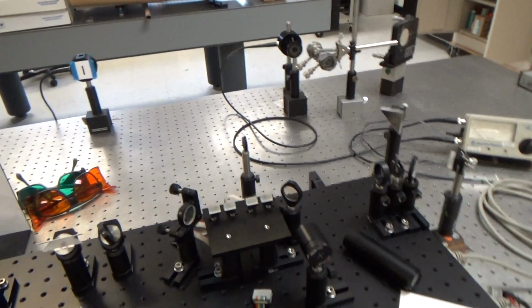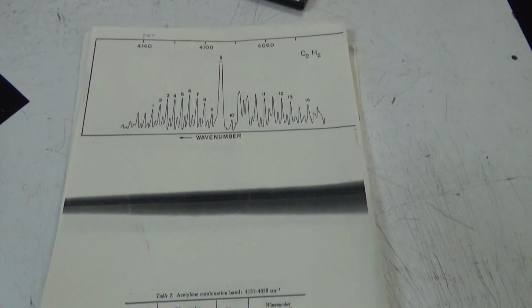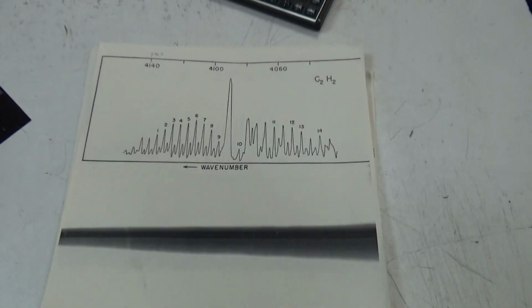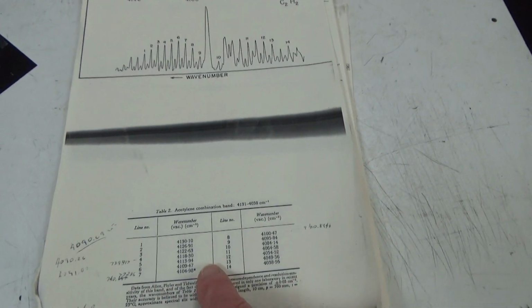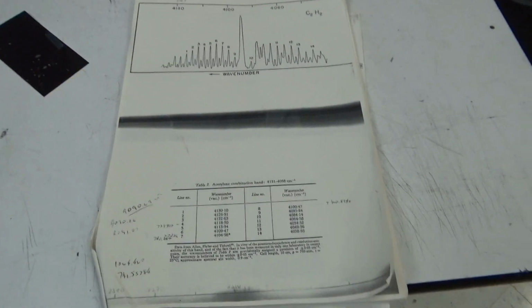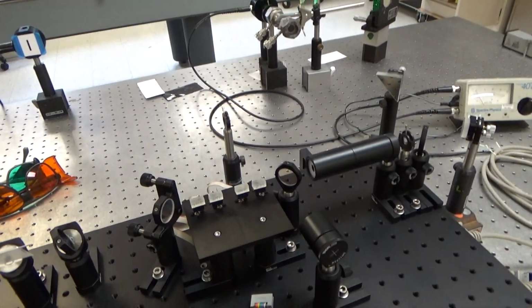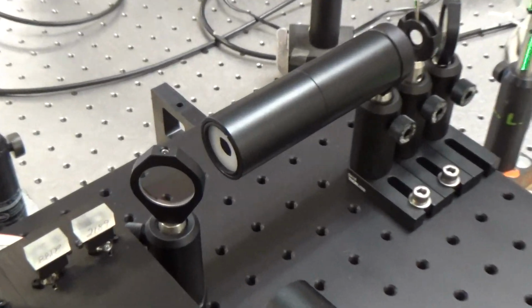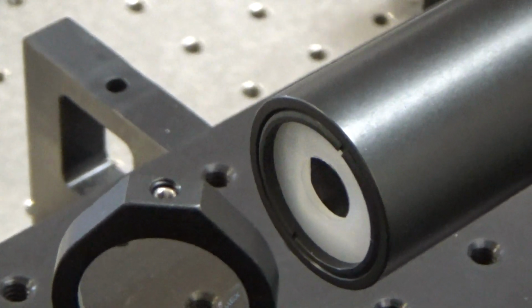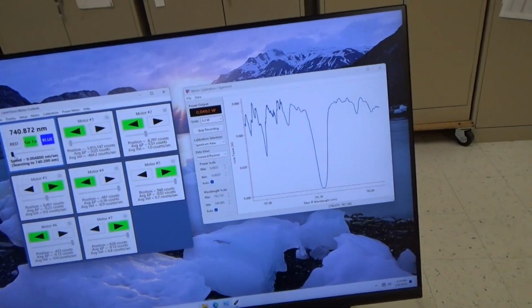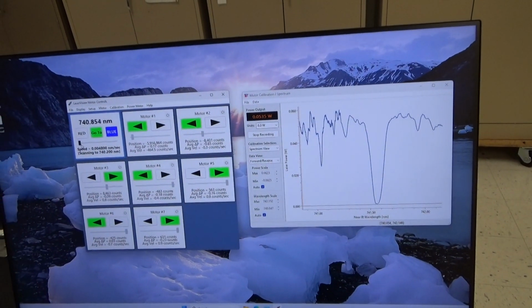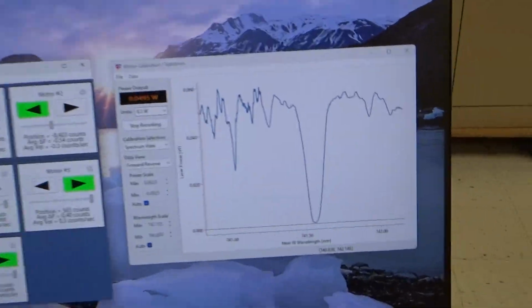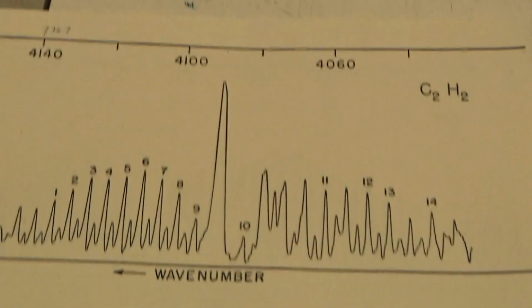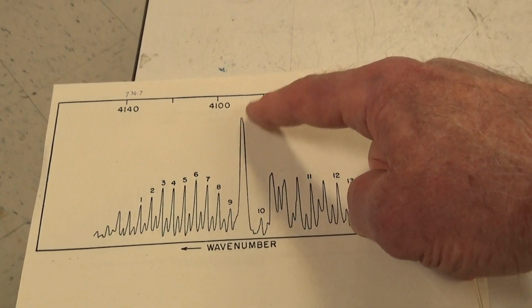And then look for the acetylene peaks that I have listed out right here. This is what you end up seeing. But I like to tune in on one of the smaller peaks here whose actual vacuum wave number is known. Okay, I've got the acetylene cell in place. I've got the stack of plates polarizer put in the C configuration, which is passing the mid-infrared light from the system. And I've started scanning already down from 745 fairly quickly, and I'm starting to see the spectral features of the acetylene.